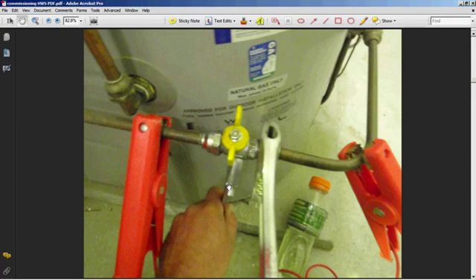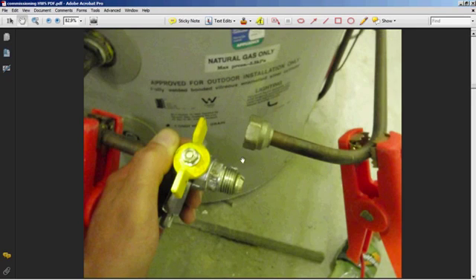Then you need to go about disconnecting the gas valve. Make sure you've got a shifter on the actual body of the valve before you disconnect the nut. What you don't want to be doing is putting pressure on the pipework when you're undoing that nut. Disconnect the valve fully, as shown here. Disconnect it fully because you need to purge the air and gas mixture out of the line. And also, if there's any dirt or grit in the fitting line, you don't want to blow that into the appliance. So disconnect the valve fully, as shown here.